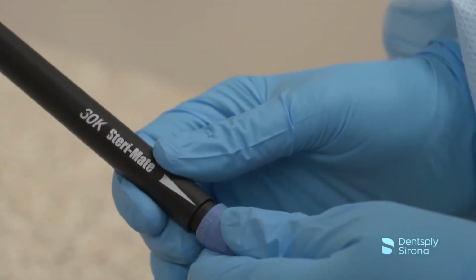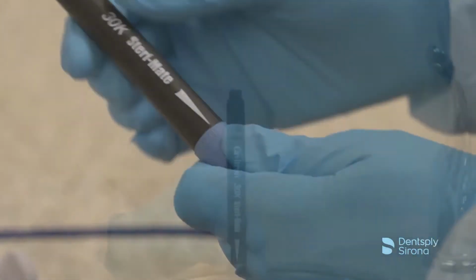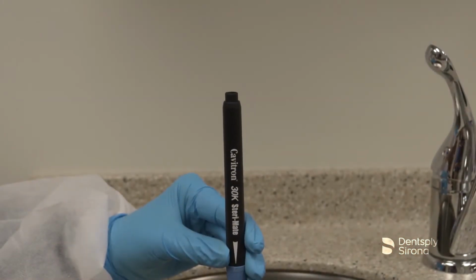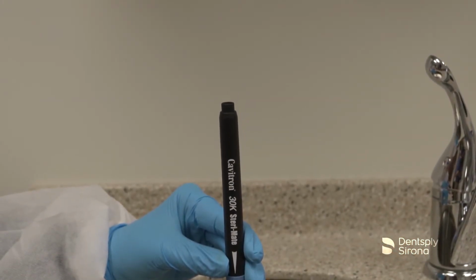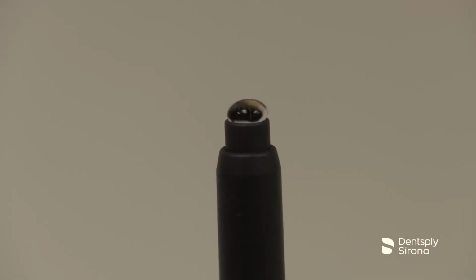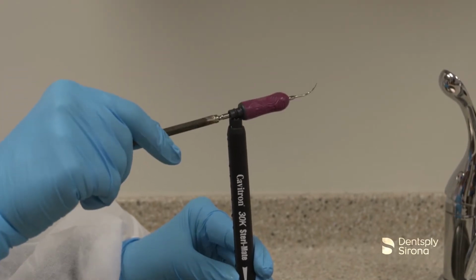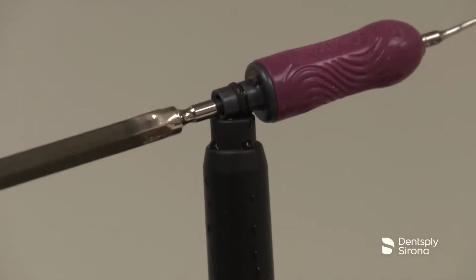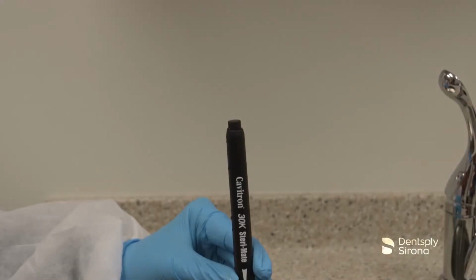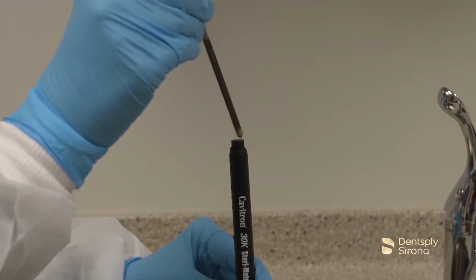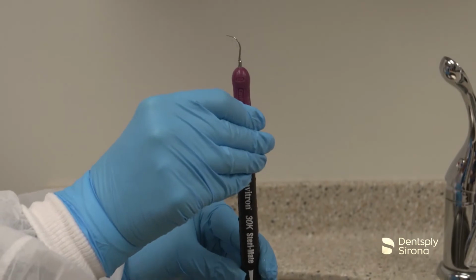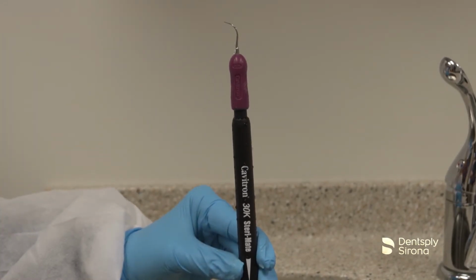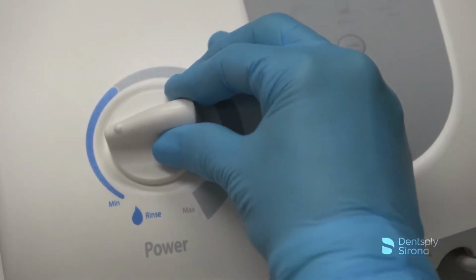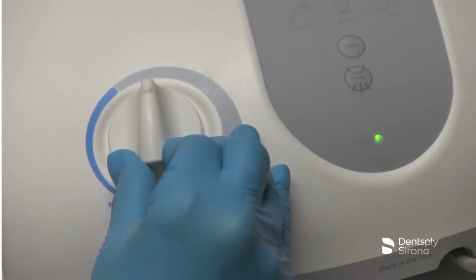To prepare the unit for another treatment session, place the sterilized Steri-mate handpiece onto the handpiece cable assembly. Prepare the handpiece for use by holding the handpiece in a semi-upright position over a sink or drain. Depress the foot pedal until the water exits to release any air bubbles that may be trapped inside the handpiece. After opening a sterilized insert, lubricate the O-ring on the insert with water before placing it into the handpiece. Fully seat the insert with a gentle push-twist motion. Do not force the insert into place. Adjust the system controls according to the recommendations for the insert selected.